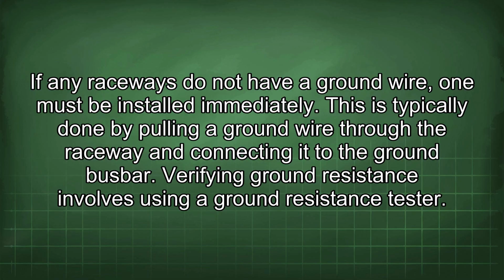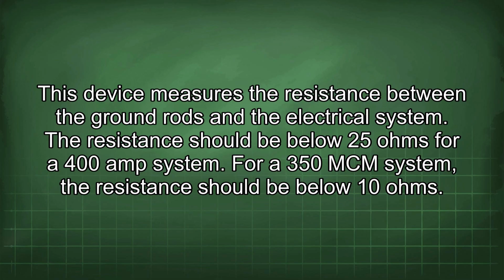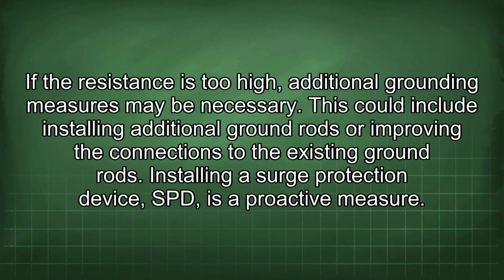Verifying ground resistance involves using a ground resistance tester. This device measures the resistance between the ground rods and the electrical system. The resistance should be below 25 ohms for a 400 amp system. For a 350 MCM system, the resistance should be below 10 ohms. If the resistance is too high, additional grounding measures may be necessary. This could include installing additional ground rods or improving the connections to the existing ground rods.